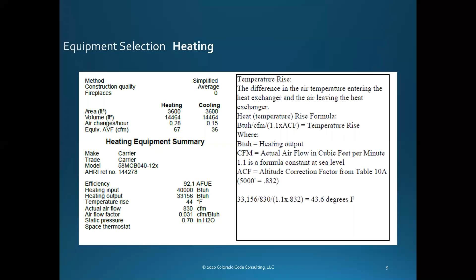And all these CFMs come from the manufacturer based on my external static pressure. So at a 0.7, it's actually moving 830 CFM at what we call heat speed, which might be medium or medium high, depending on what my temperature rise is. So this is just a formula. If you want to do the math, fine. I just put it in here because that's what the software is doing. It at least has a clue as to what that is, because it's just math as long as the designer puts in the right heating output.